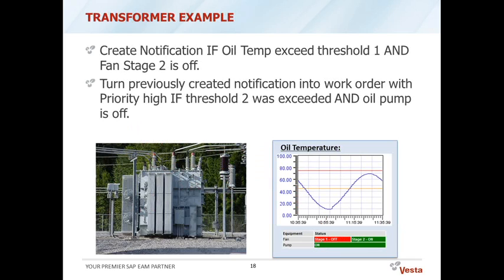The last example I have in my list here is a classic utility transformer example. Transformers usually have an oil cooling system, and what we have here is essentially a situation where we want to be notified if the oil temperature exceeds a certain threshold.